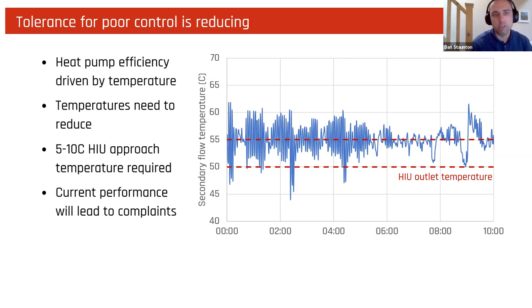However, the tolerance for poor control and poor stability is reducing. We're moving to heat pump led heat networks. Because of the impact on heat pump efficiency, we're needing to drop temperatures. Whereas traditionally we'd have had a 10 to 15 degree approach temperature from the secondary flow onto the HIUs, we're now looking more towards 5 to 10 degrees to retain efficiency on the heat pump.